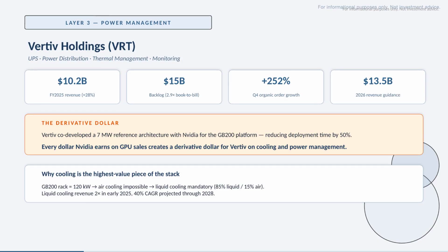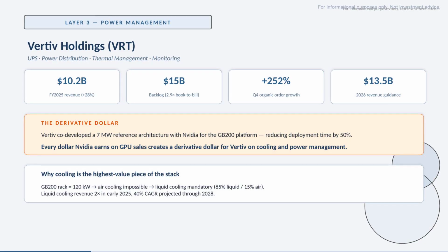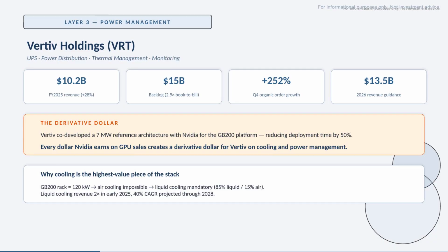Here's why cooling is suddenly the highest value piece of the stack. That GB200 AI rack drawing 120 kilowatts, you physically cannot cool it with air. The laws of thermodynamics don't allow it. You need liquid cooling, water or dielectric fluid piped directly against the silicon.